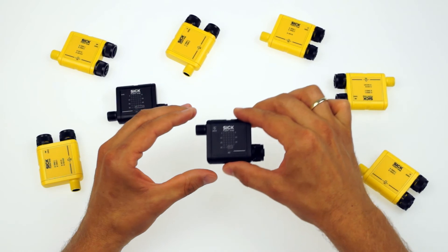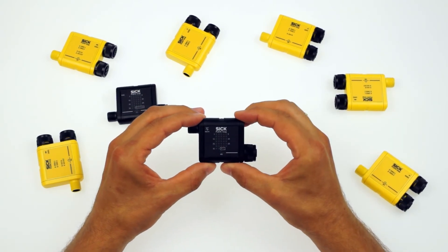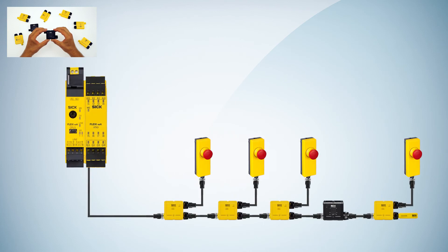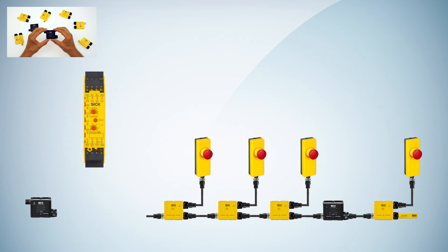Now let's talk about the master node. Up to now FlexiLoop has been working in combination with the software-programmable FlexiSoft safety controller. With the master node it is also possible to use FlexiLoop together with the FlexiClassic safety controller, which is configured by a rotary switch. Therefore the master node works as a kind of translator between FlexiLoop and FlexiClassic, and it always has to be the first node within a FlexiLoop cascade.